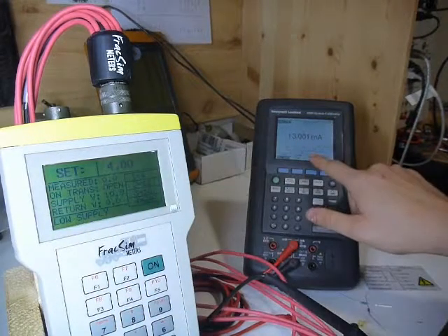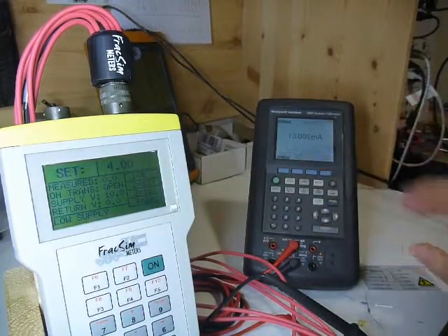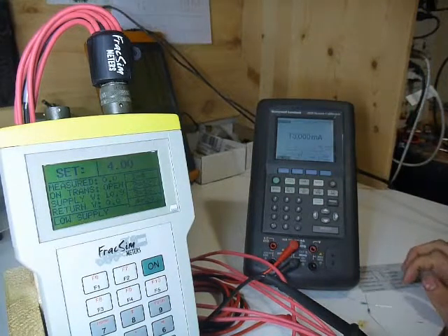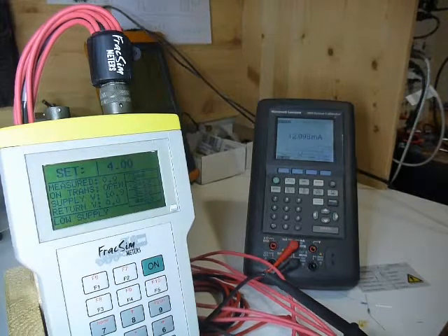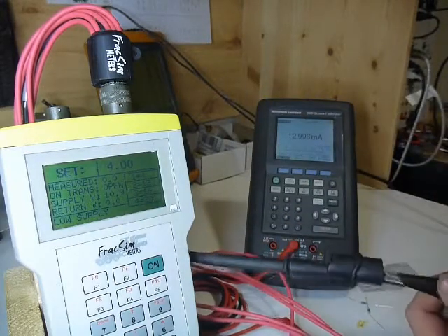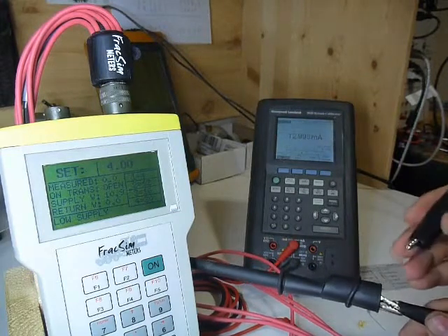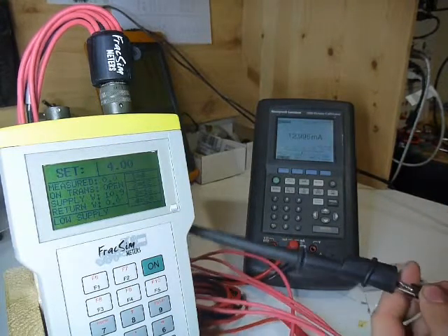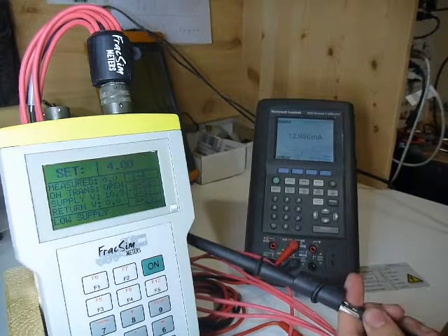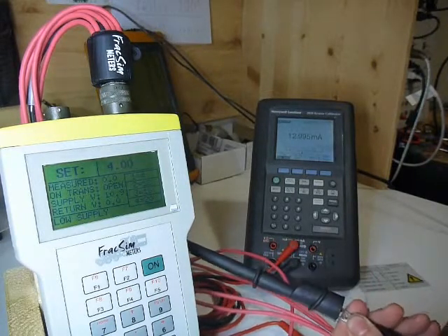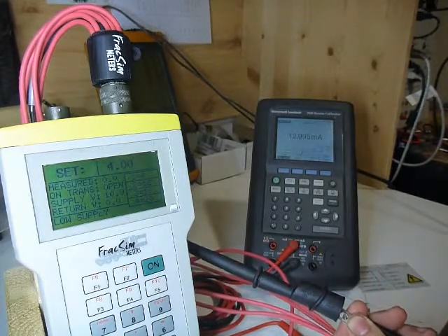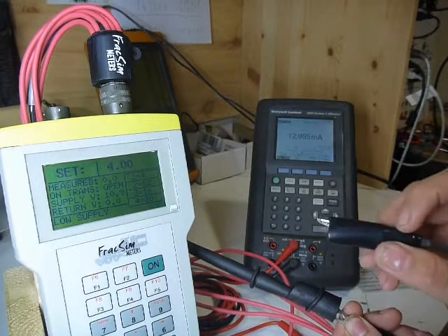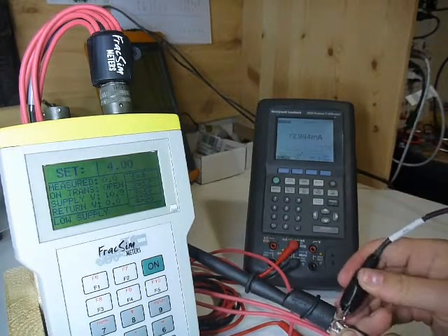3-wire current sim. So you see the screen changes a bit, and our current is way out to lunch. It's not working right. It's essential, if you're using 3-wire current sim, it will only work correctly if you have that ground wire from the Fracsim hooked up to ground of the unit. And of course, ground of the unit, in this case, is the ground of the power supply. Keep in mind, 3-wire current sim will not work on systems that go through optically isolated barriers or intrinsic barriers or stuff like that, because frame ground is no longer a ground, so it will not work correctly.